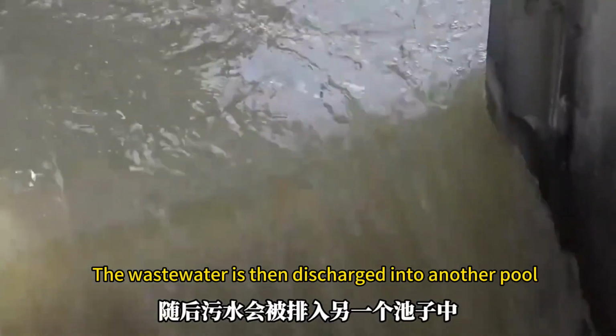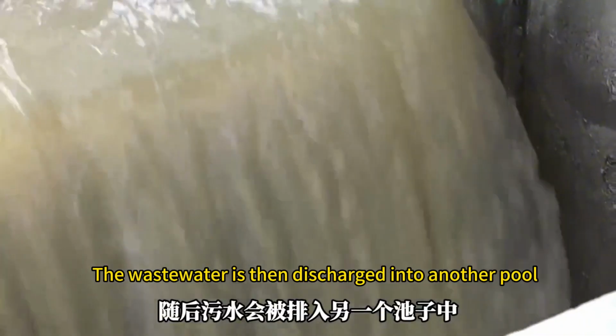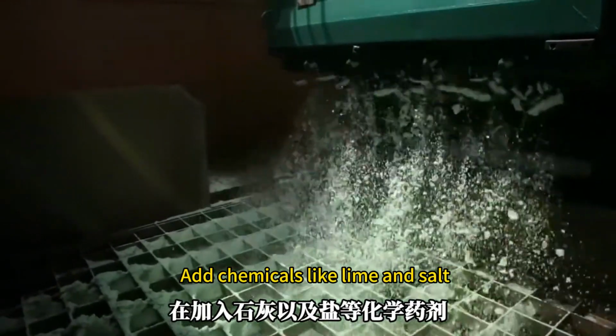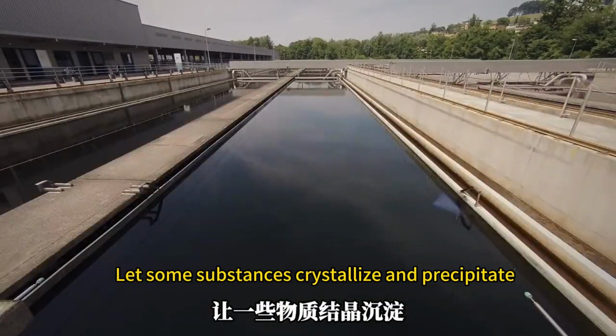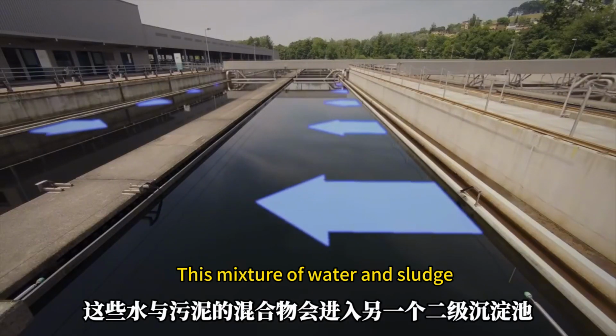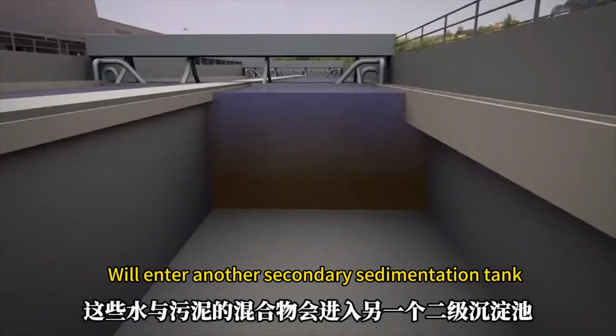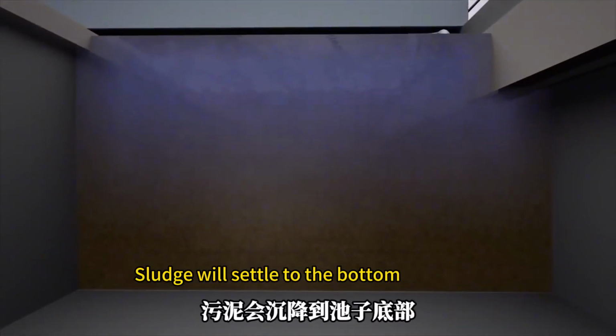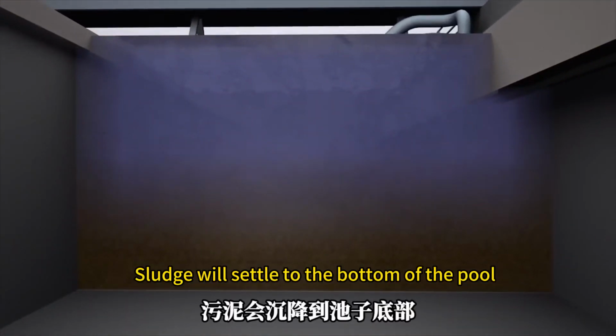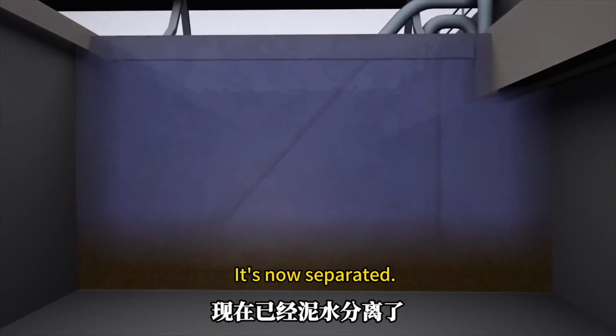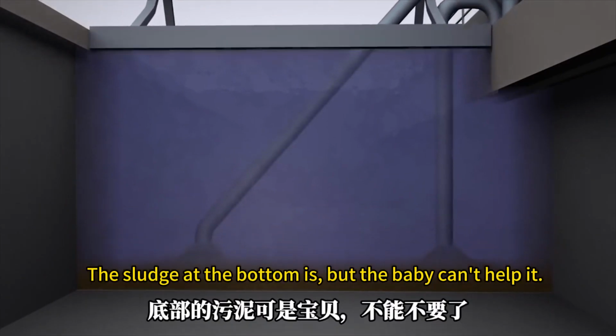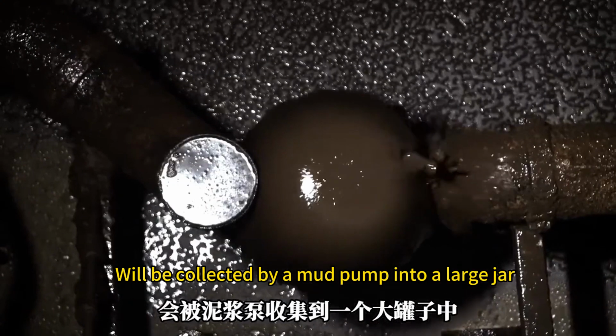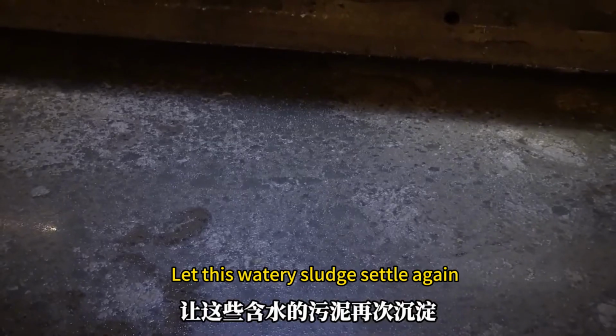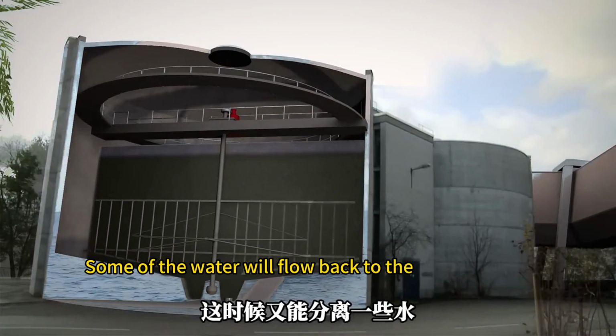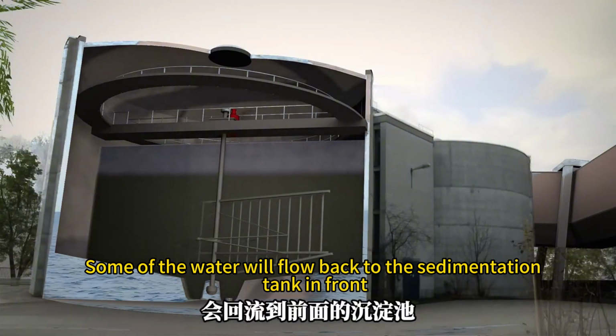The wastewater is then discharged into another pool. Add chemicals like lime and salt. Let some substances crystallize and precipitate. This mixture of water and sludge will enter another secondary sedimentation tank. Sludge will settle to the bottom of the pool. It's now separated. The sludge at the bottom will be collected by a mud pump into a large jar. Let this watery sludge settle again. It can be separated again. Some of the water will flow back to the sedimentation tank in front.